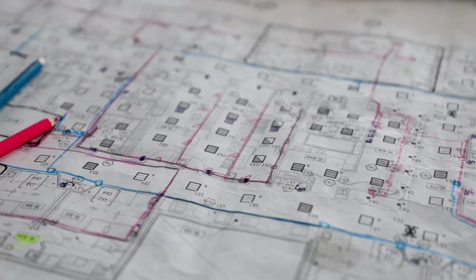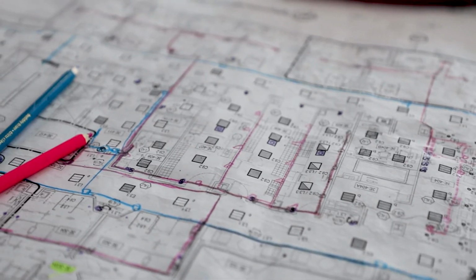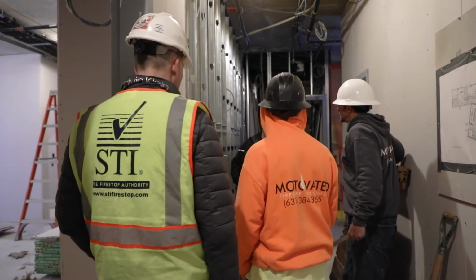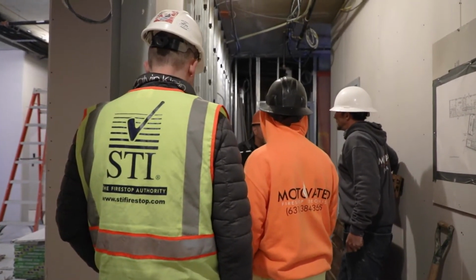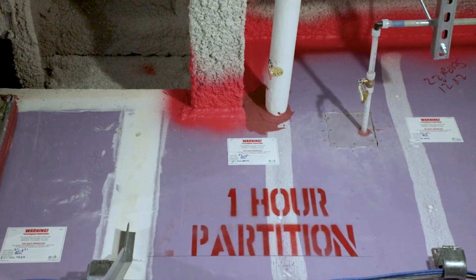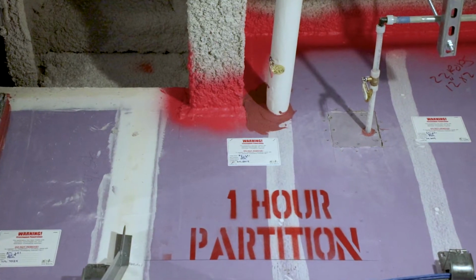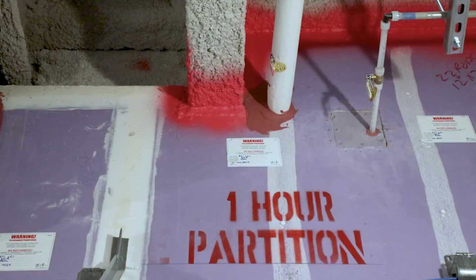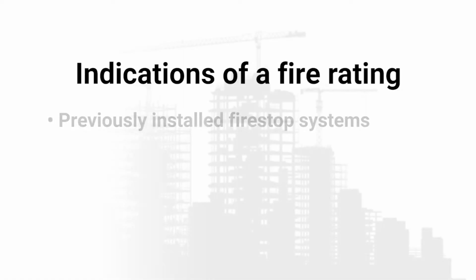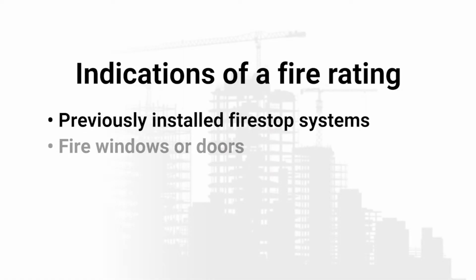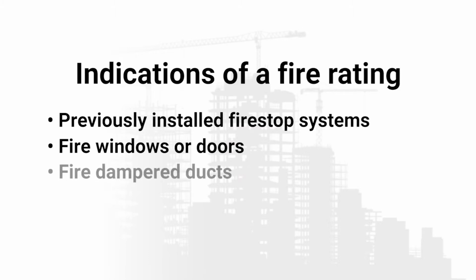Often, in new construction, it's easy to find the life safety drawings to identify the rated assemblies and their corresponding hourly rating. However, in renovation projects, where drawings may not be available, you can look for indications of a fire rating, such as previously installed Firestop systems, fire windows or doors, fire damper ducts, or even wall stenciling.